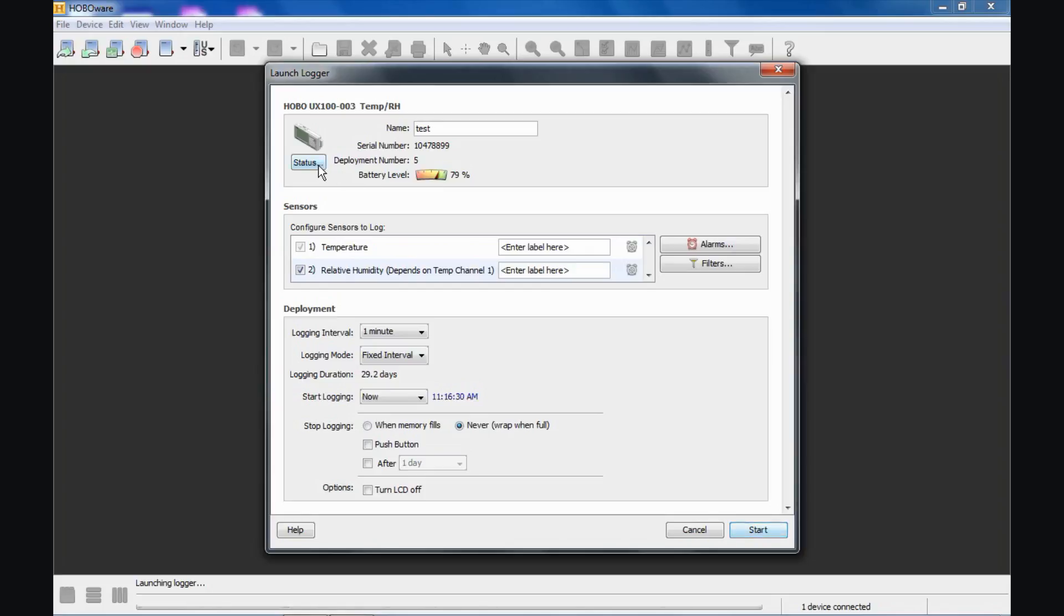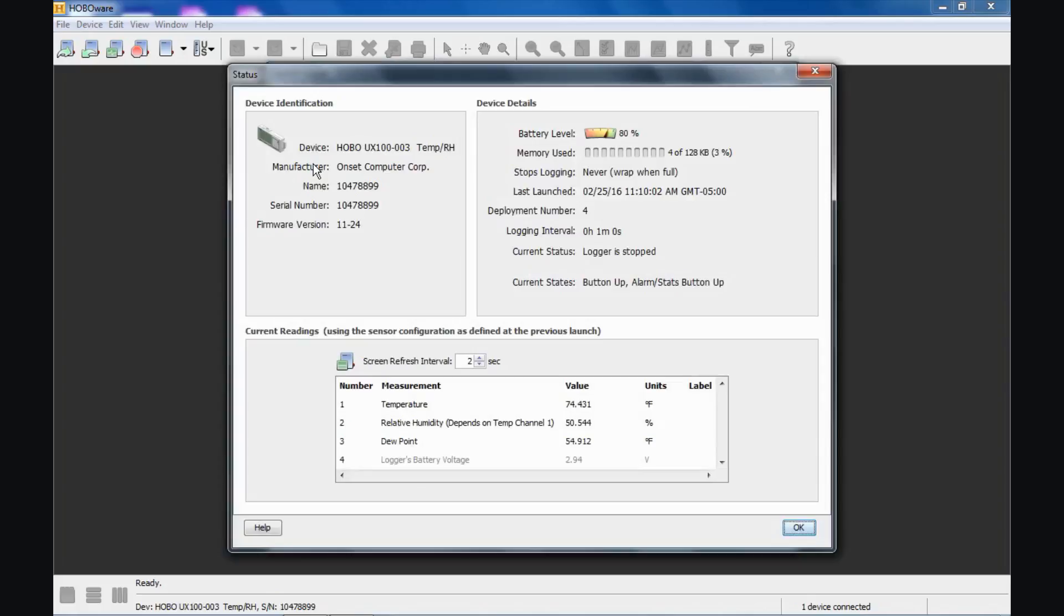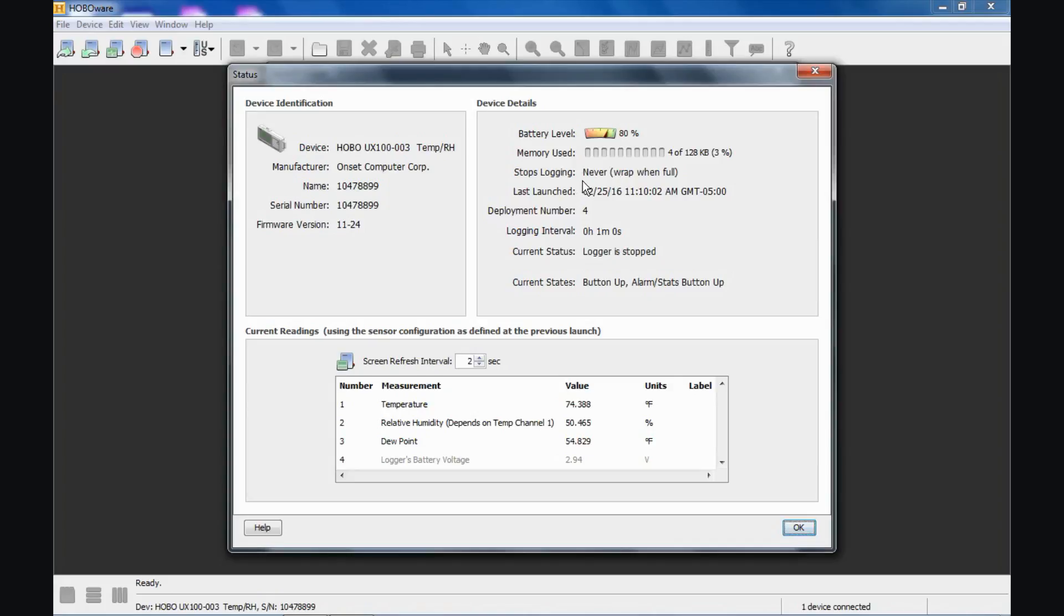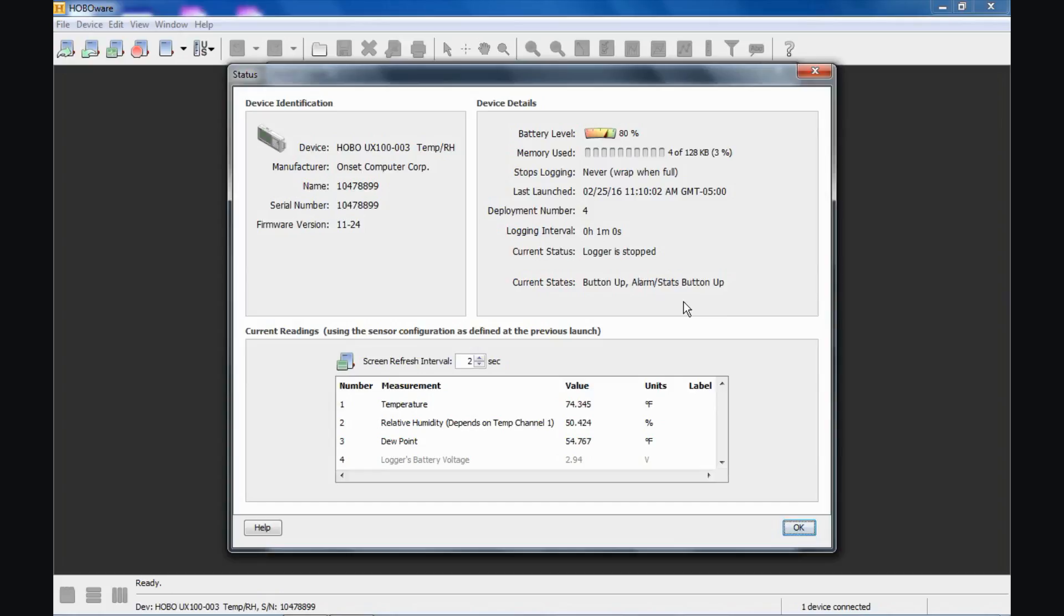We talked about status. There's a status screen. You can get to that from the launch screen as well if we click on status. Basically what this does is it gives you the information about the data logger, the model number, the serial number, the version of firmware that's in the logger itself, which is the software in the logger. The previous name—again, it was a serial number which was used for the previous deployment. What the battery level was for that deployment the last time it was deployed. Again, how it was configured as far as how it was configured to stop, how it was configured for a logging interval, which is one minute. When it was launched. The deployment number at that time. And it also tells us the current status of the data logger, which is right now it is not logging. It is stopped. And then some information about internal events.